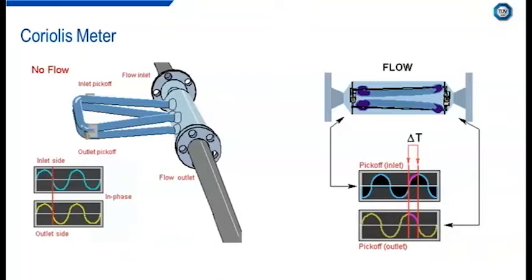A Coriolis meter consists of a vibrating flow tube through which the fluid passes and an electronic transmitter which monitors and maintains the flow tube oscillation by generating a suitable drive signal. In the absence of flow, the inlet and outlet sections of the flow tube vibrate in phase with each other. A phase shift between the inlet and outlet sections occurs when the fluid flows through the vibrating flow tube, which is directly proportional to the mass flow rate of the fluid. Two sensors monitor the flow tube vibration as the process fluid flows through. The electronic transmitter collects the sensor signals and carries out the mass flow and density calculations. The exact frequency of the flow tube vibration depends on the density of the fluid and can be determined by measuring the frequency of oscillation of the tubes.